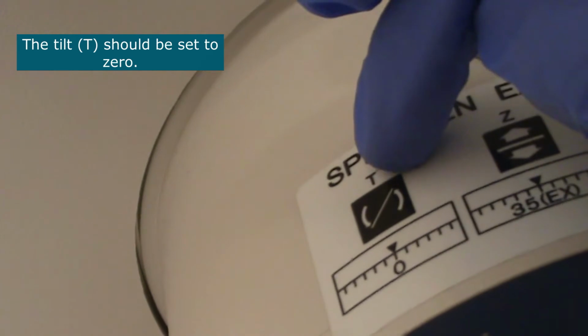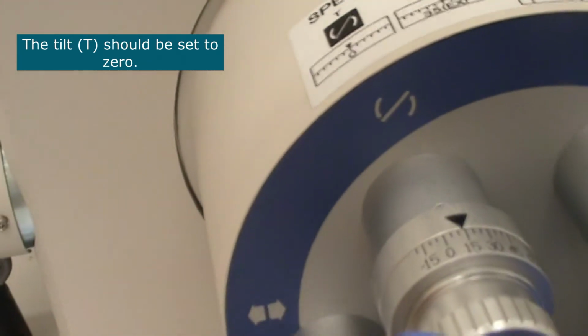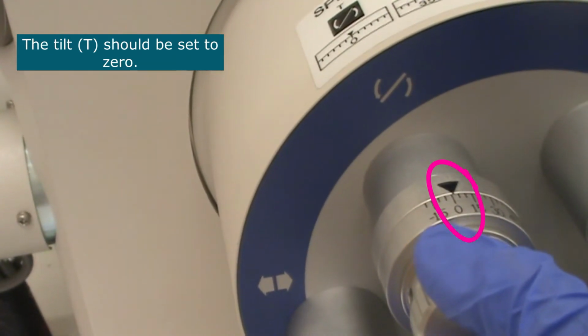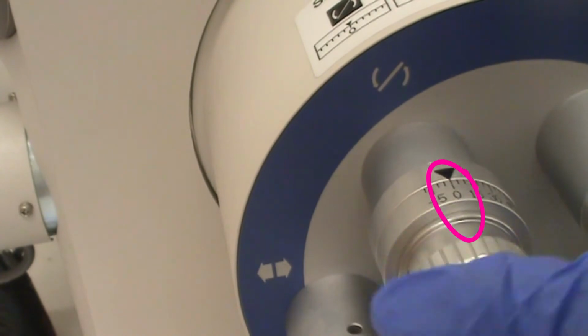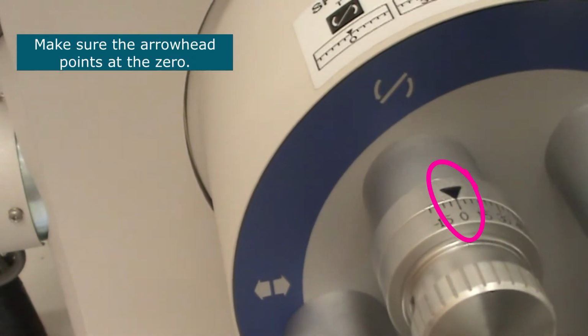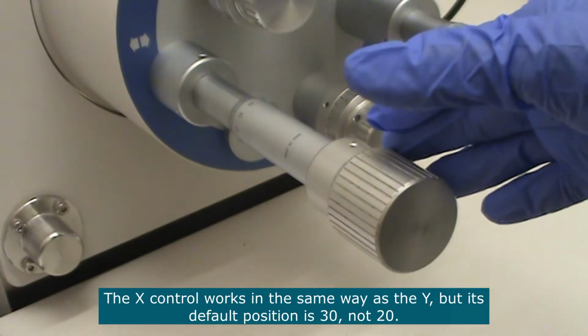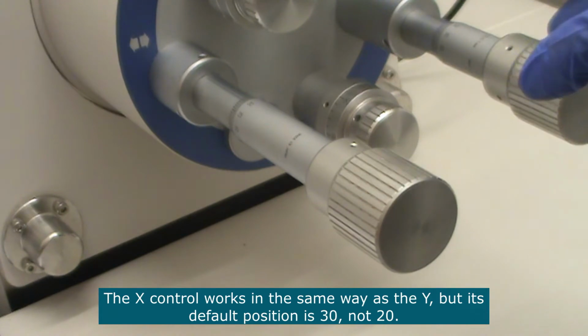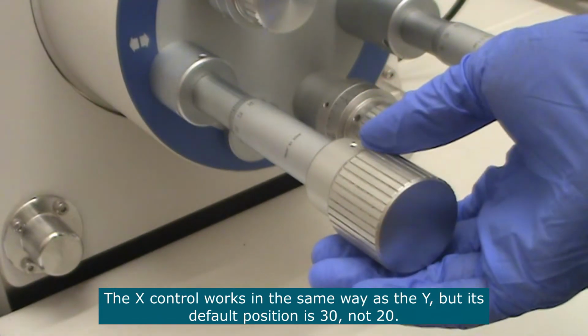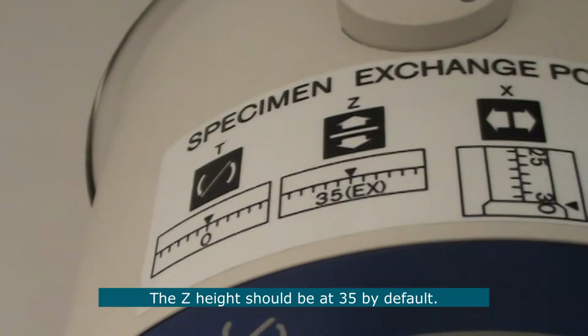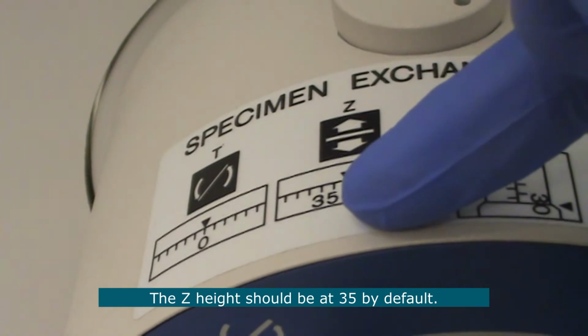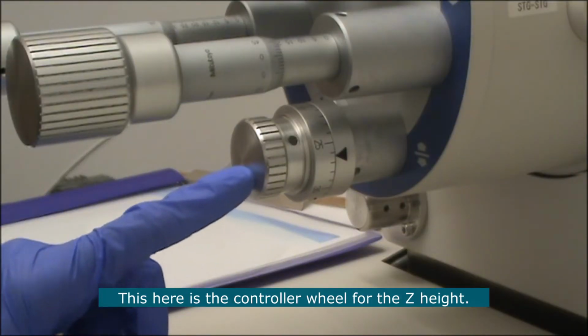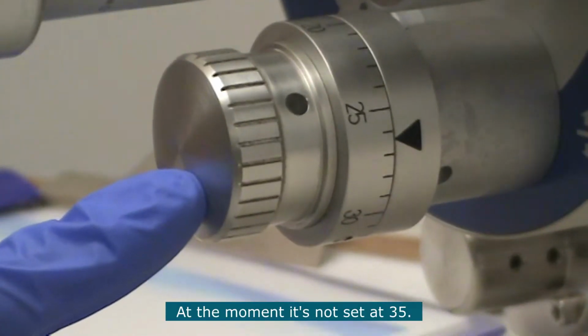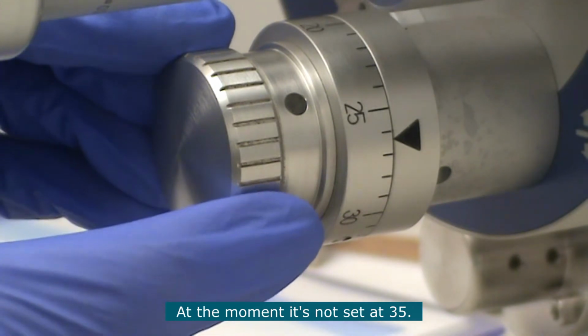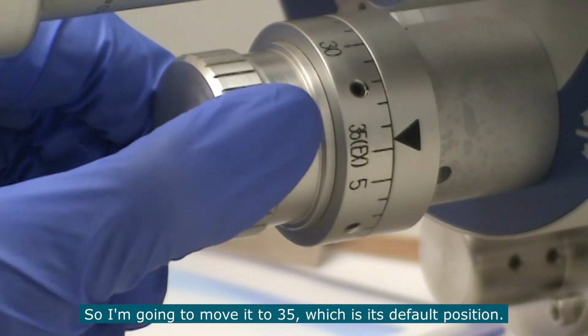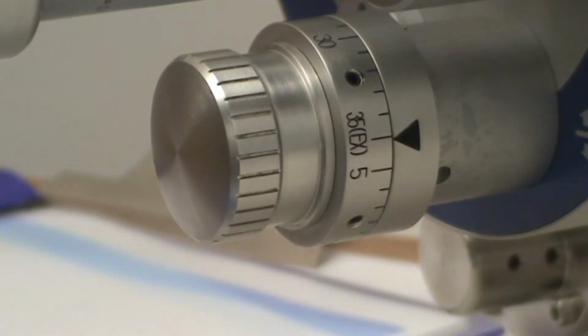The tilt, so you can see here a T for tilt, which is this control here, should be at 0. So make sure the arrowhead is pointing at the 0. The X control here works in the same way as the Y control, but it's set to 30 as its default position, so you should make sure it's at 30. The Z height should be at 35 by default. This here is the controller wheel for the Z height. At the moment, it's not set at 35, so I'm going to move it to 35, which is its default position, before I insert the sample.